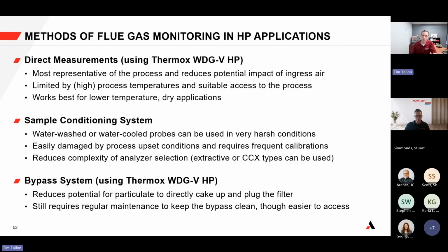Also, a sample conditioning system would be a different type of technology, more of an extractive or close coupled extractive type. Water flush probes, water cooled probes support different applications for high particulate, and that might be more for an extractive type. We have different versions of the WDG-V.